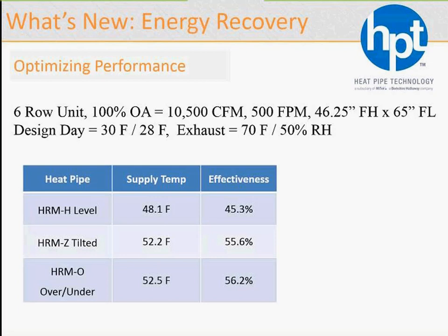The level, supply temp 48, and it increases and increases. It's the useful, obviously, side of the heat exchanger. We don't really care what's happening on the exhaust side, but it should be very similar to the pre-cool, provided condensation is not taking place.